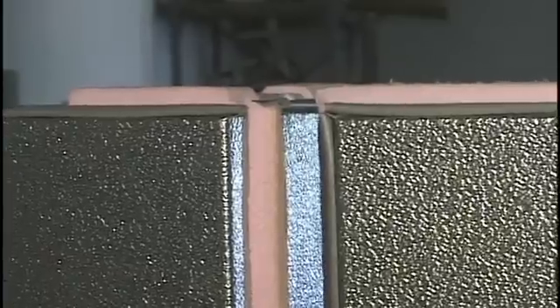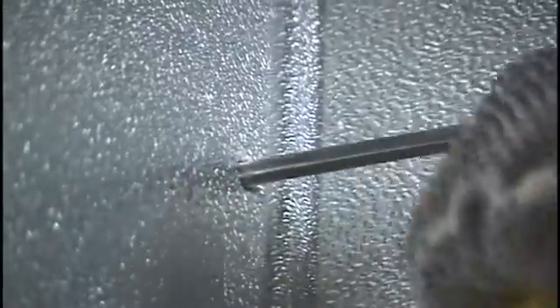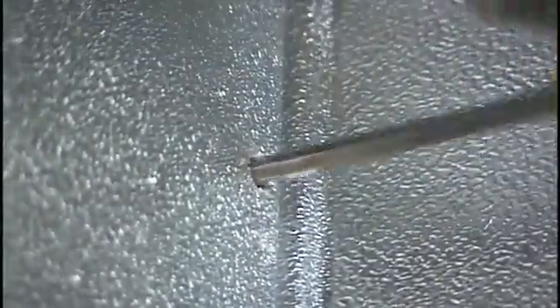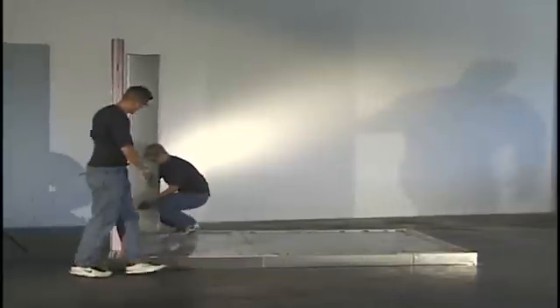It is important that the wall panels are flush on the sides and top. Lock the wall panels together. Do not lock the wall panels to the floor at this point — this will give more room for adjustment as you assemble the cooler.